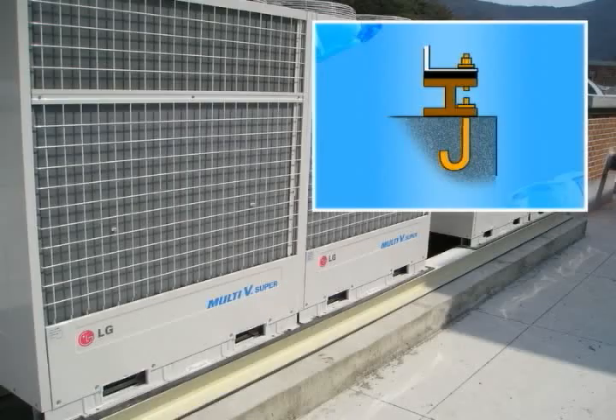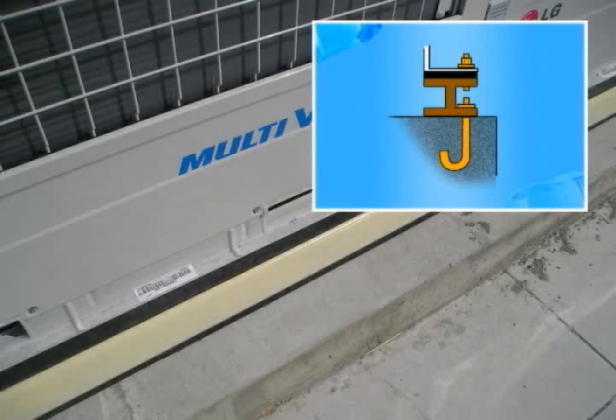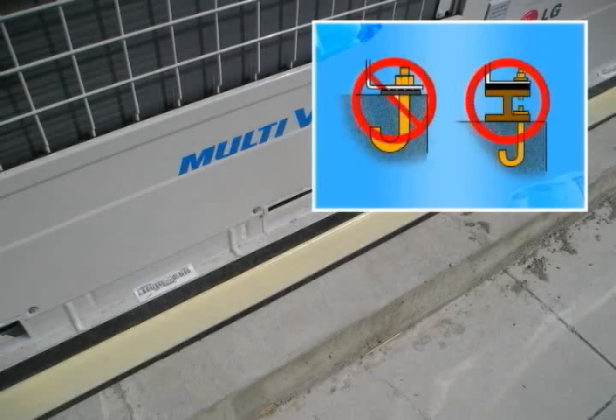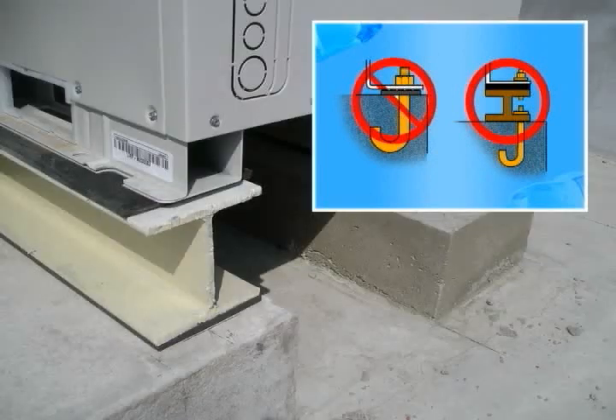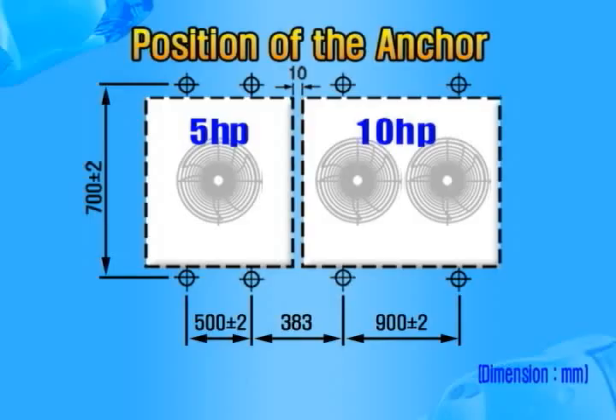Fix the outdoor unit with bolts so that it does not tilt over in strong wind. Use H-beam for the main support and anti-vibration pads to cut the vibration. The gap between the anchor bolts on the support of the outdoor unit is 500 millimeters for the front and back line of 5 horsepower. For 10 horsepower, 900 millimeters, and the distance between front and back should be 700 millimeters.